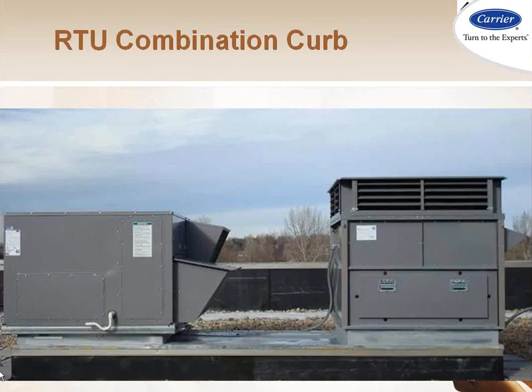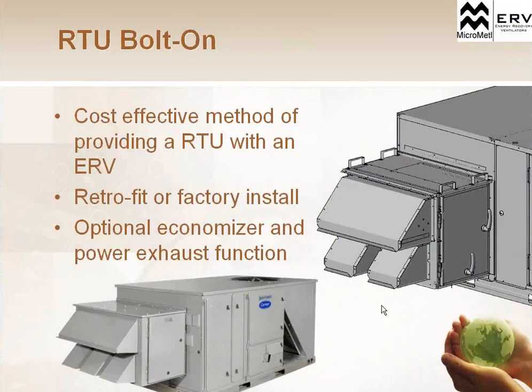Here's a picture of a direct installation of that. You can see the flashing on the roof right here. You can see this combination roof curb, and then we drop the rooftop unit on, and the energy recovery unit directly on, and all that duct transition is done inside that roof curb. So it's a very easy installation, especially for new applications, even for retrofit type applications. A single roof curb that you drop on both pieces makes it a really quick installation.